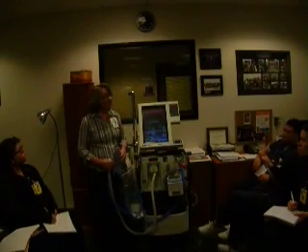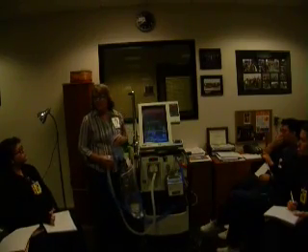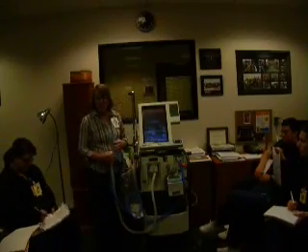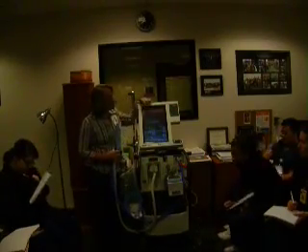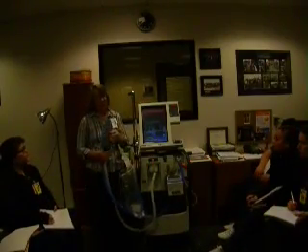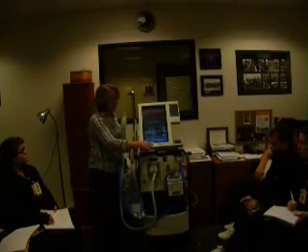You'll get to know your ventilator and your alarms, especially depending on where you go to work. I'm going to show you the differences in the alarms, but this is high priority. You can tell by the sound of it. Also, anything that comes up in red on the screen is high priority. That means you get in there quick because there's a serious problem with the ventilator and you need to find out what it is.